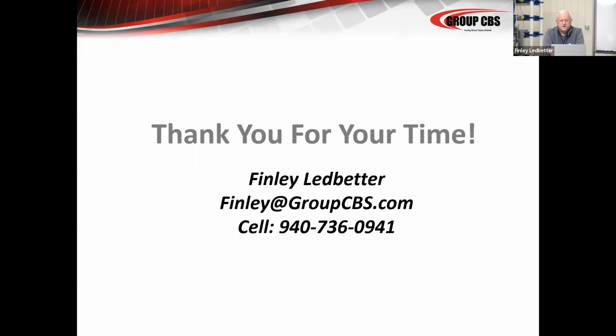And if I don't know really what you're dealing with, it's hard for me to recommend to you what to do. But a good visual inspection, keep them clean, look for cracks, do an acoustic test, do PD testing, do the sorts of things to tell you that there's no breakdown, no corona effect right now. What PD does, PD is a capacitive discharge that's constantly damaging the insulation. Once it trees, it becomes kind of a corona discharge. Then you get acids and you get the treeing effect and the things that you visually see.